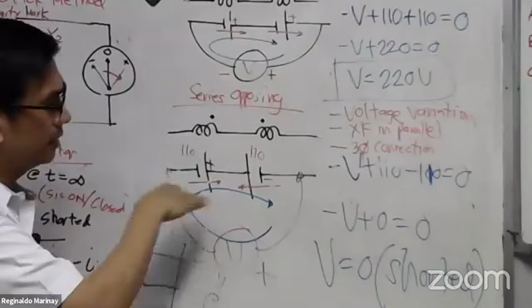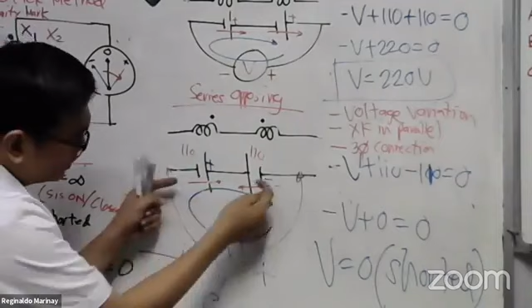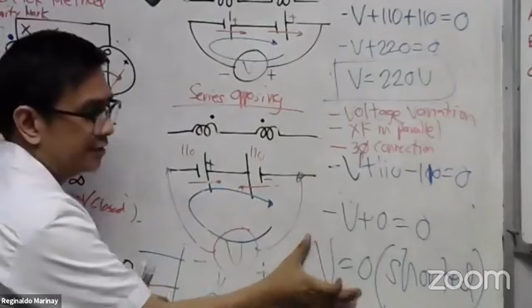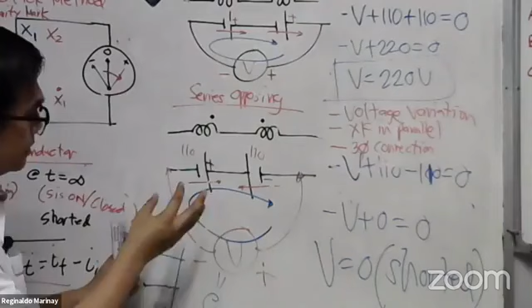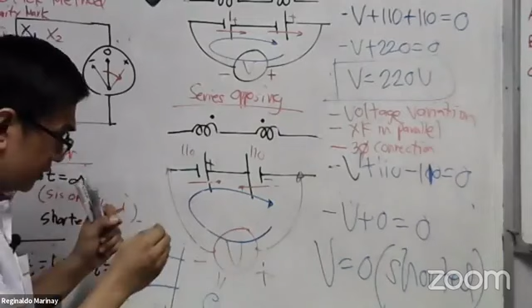So when you accidentally change its connection, just like this basic example, because these two coils have 110 volts, 110 volts rating. If you connect it this way, just like two batteries connected this way, it's the same principle. You will come up with 0 volts because they are opposing each other, magka-kontra sila. I already proved this using Kirchhoff's voltage law here. You will see the two batteries oppose, or this represents the transformer coil here. If you connect it wrongfully, the worst case is you will come up with a short circuit.